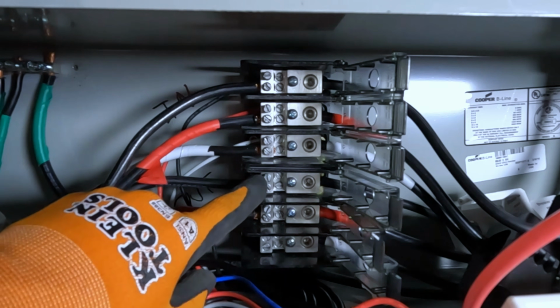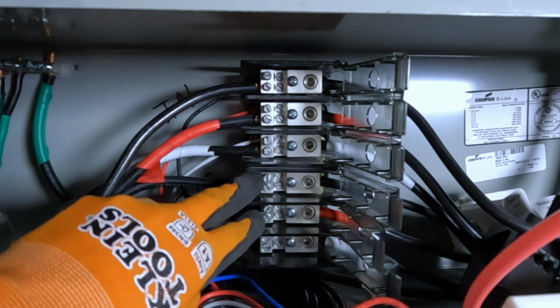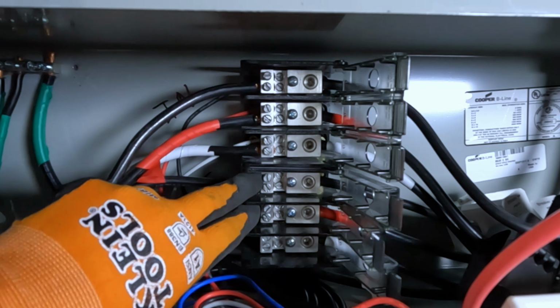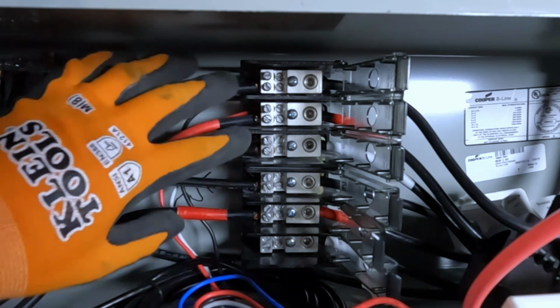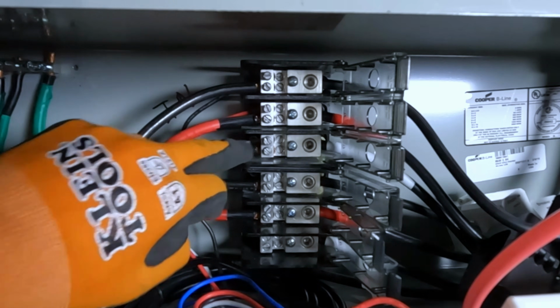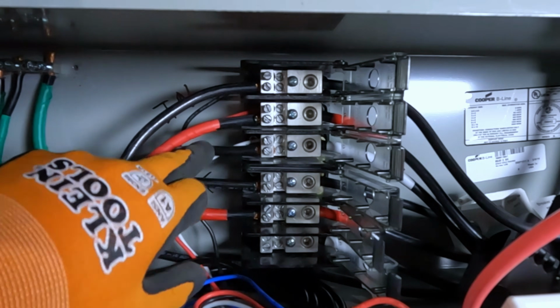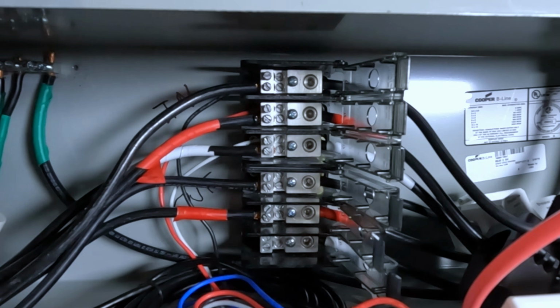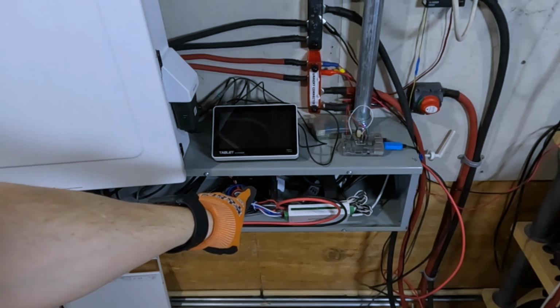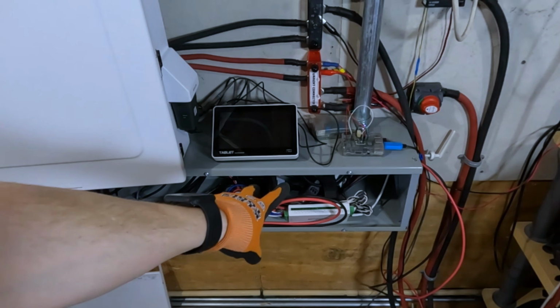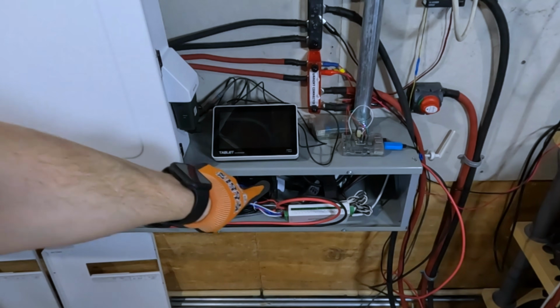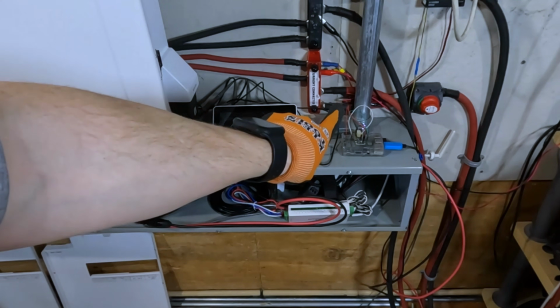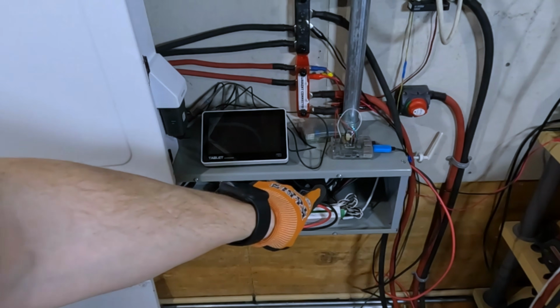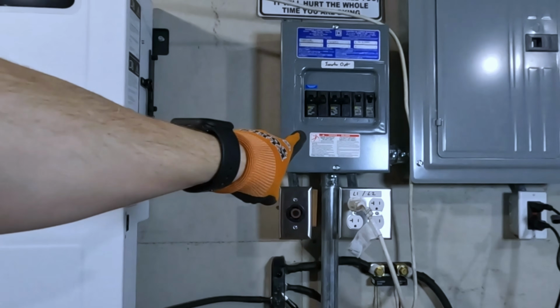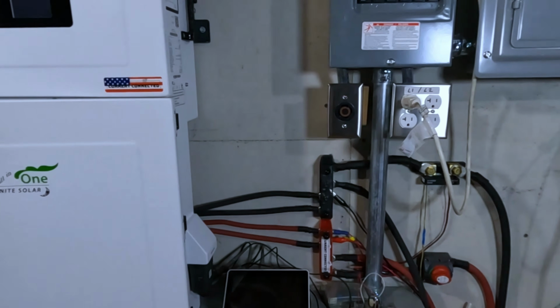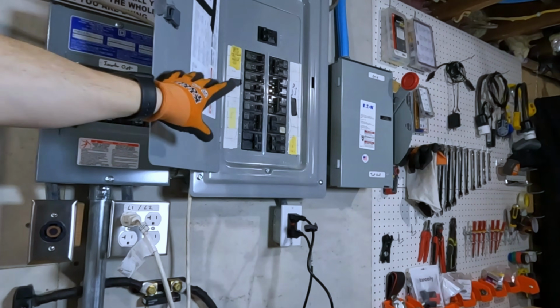So we will have L1 and L2 for the output of the second inverter. And then the same thing as well with the inputs, L1, L2, and neutral. And since it's a common neutral, I do have only a single neutral running over there as opposed to multiple neutrals. So then your output of that PDB, the combined output of both inverters, you would run 1 set of wires, L1, L2, neutral, and your ground, out of that block, and then you would take it to your critical loads panel. From the input standpoint, this is my grid breaker panel.